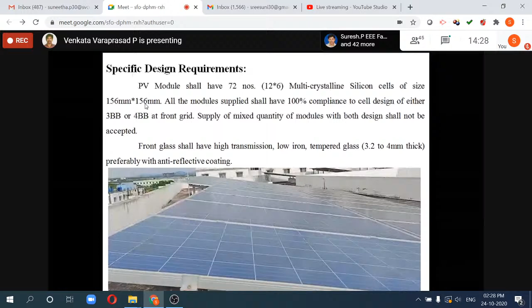Specific design requirements. The PV module shall have 72 multi-crystalline silicon cells, each of size 156 mm by 156 mm. All the modules supplied shall have 100% compliance to a cell design of either 3 bus bar or 4 bus bar at the front grid. In practice, the erected modules have 4 bus bars at the front grid. The supply of a mixed quantity of modules with both designs shall not be accepted. Front glass shall have high transmission and low iron. If the iron content is more, the module body temperature increases. That's why it is low iron tempered glass with a thickness of 3.2 to 4 mm, preferably with anti-reflective coating.